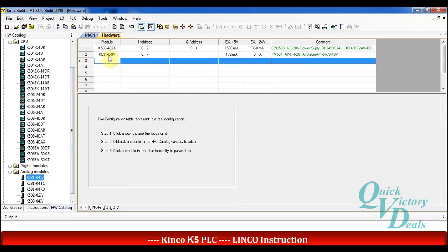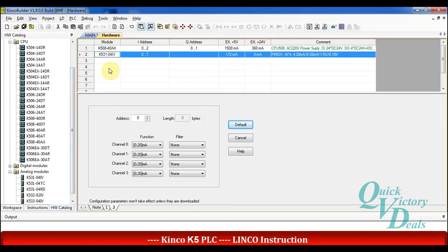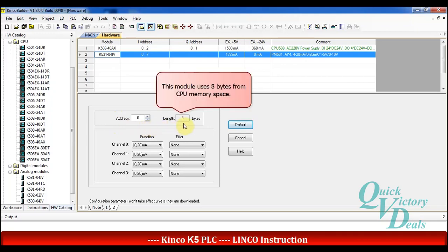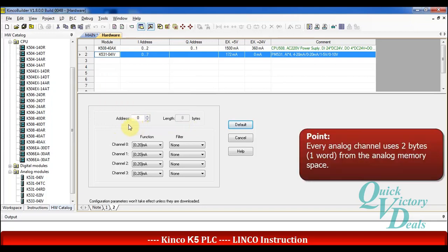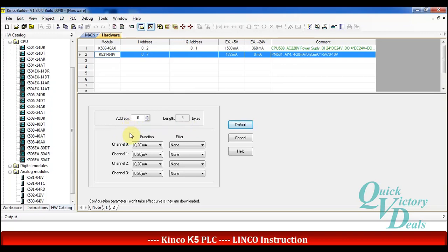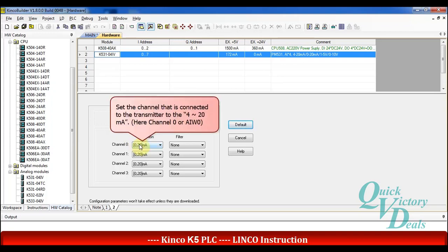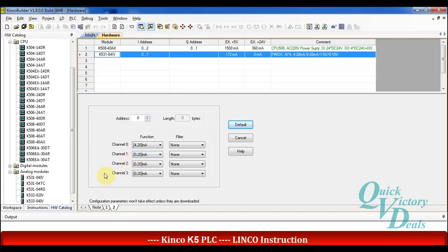After clicking on this module we can see the settings. We can see that it needs 8 bytes from the CPU memory and the address starts from 0. Every channel uses one word. For this example we will set one of the channels to the 4 up to 20 mA range. Channel number 0 means AI word 0. Then return to the main window.